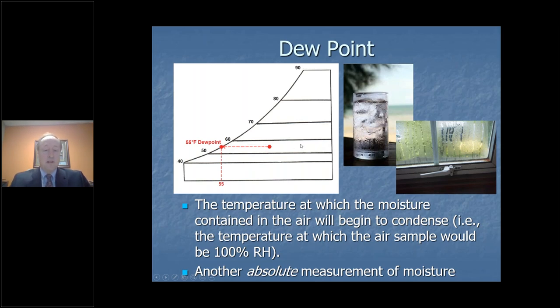But what is the dew point? The dew point temperature is the temperature at which the moisture level in that air is such that it will begin to condense, go from a vapor to a liquid when it touches something of that particular temperature. Now you'll see a glass of ice water here, which is very common for you, I'm sure, to see all the condensate dripping on the outside. And that is because the dew point of the air that is surrounding this cold surface is higher than the temperature of the surface, so it begins to condense. We see this on our windows often as well, when the dew point temperature outside of the building is much higher than the surface temperature of the glass windows. But that's the absolute moisture level, either humidity ratio or dew point.